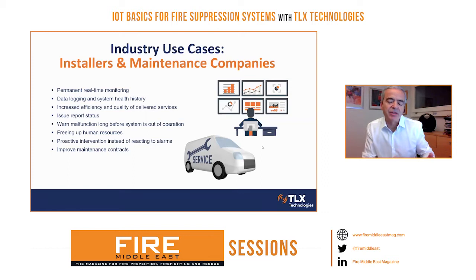So imagine what would happen today. You wouldn't have that information until that leak became a 10% loss in that specific tank, and that opened a pressure switch or a connected pressure manometer and gave an alarm to the panel. But there would be no information today. So a service technician should go on site, explore what the failure is, identify which cylinder, what type of cylinder, what type of agent, then go back, prepare a spare, and come back to resolve the issue. All of that time, the system was out of order because it's already in alarm. Most probably that system went out of operation, maybe putting an industrial process out of protection.